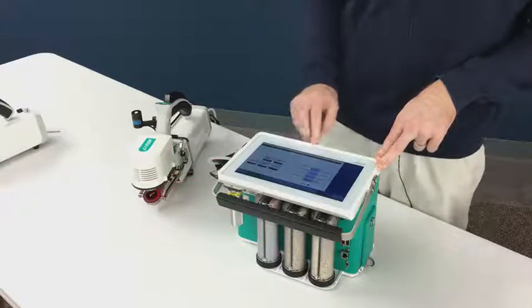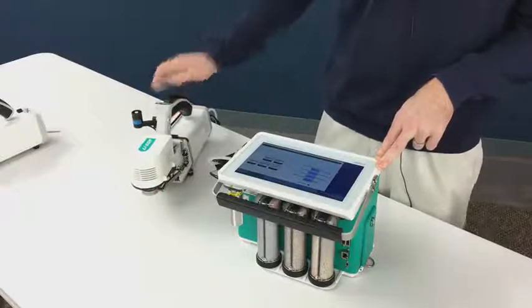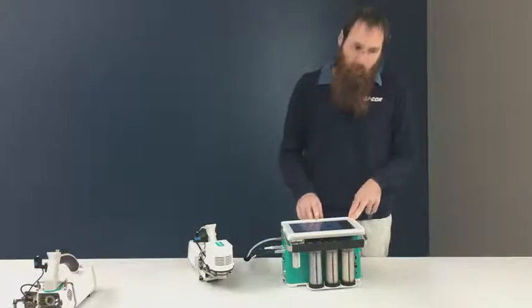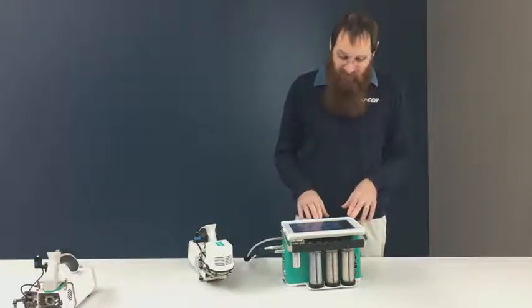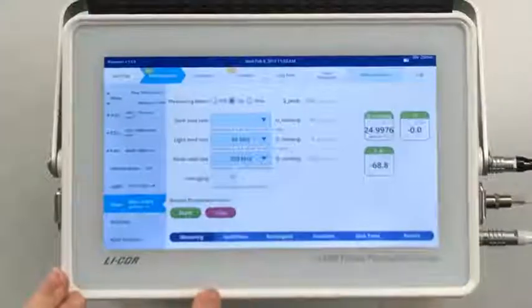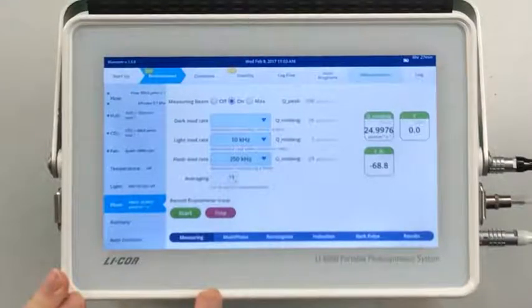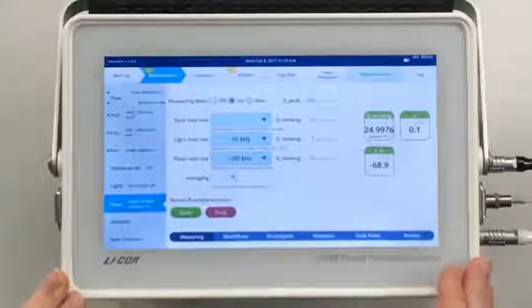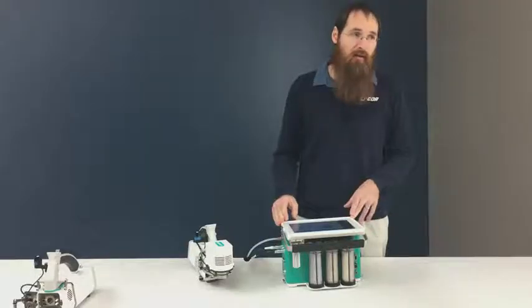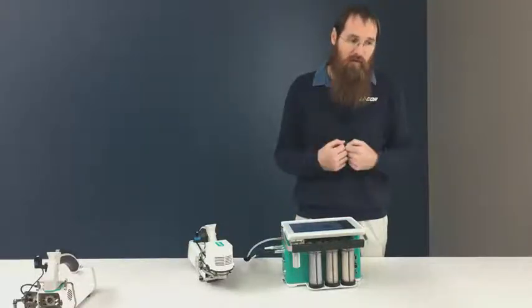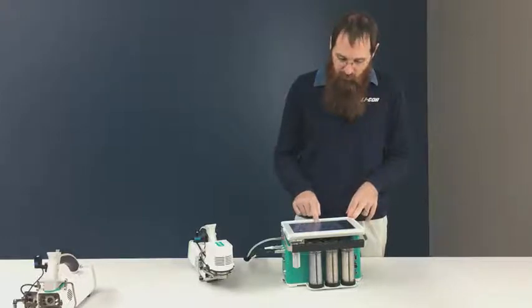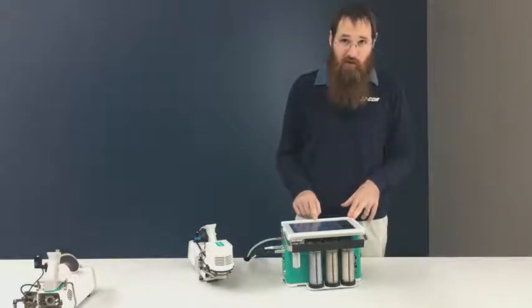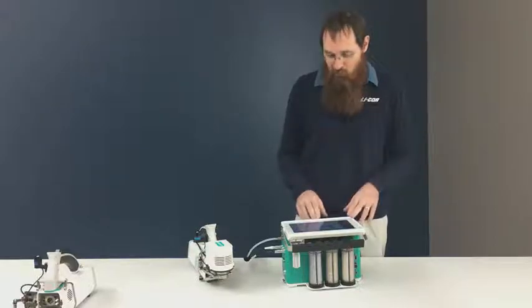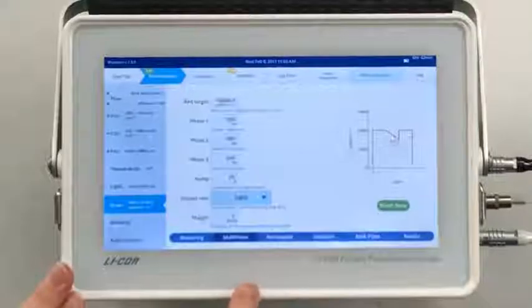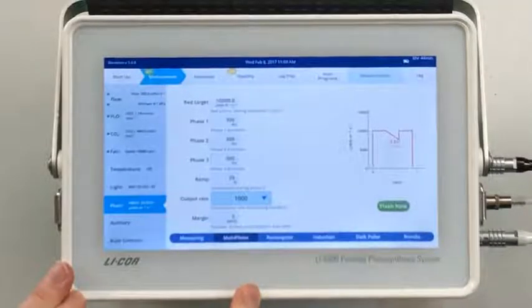Right. And then I can turn that light off. For configuring the fluorescence part of the measurement, we have another sub-menu that shows up down here. This lets us configure the measuring light, the modulated light that's used to generate the fluorescent signal that we detect. We have options for rectangular flashes. This is like a traditional fluorescence measurement. We have options to configure the multi-phase flash.